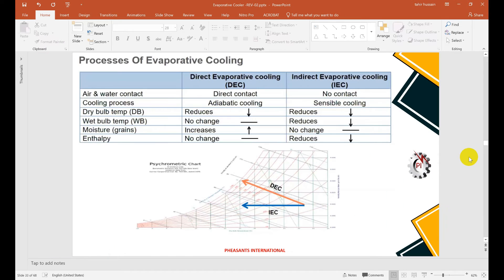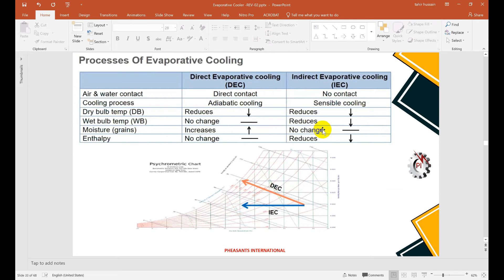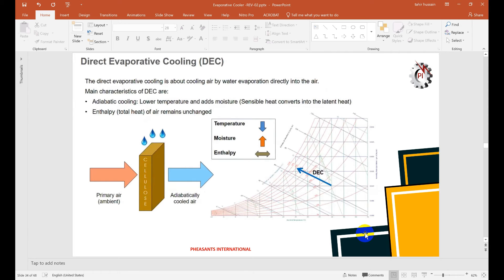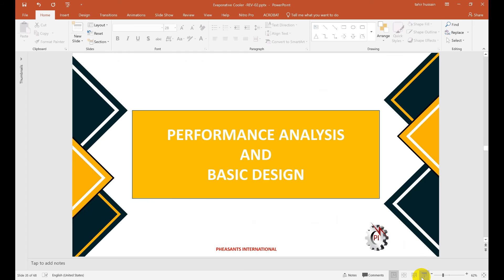In direct evaporative cooling (DEC): direct water-air contact, adiabatic process, dry bulb temperature reduces, wet bulb temperature stays constant, moisture content increases, enthalpy remains constant. In indirect evaporative cooling (IDEC): sensible load reduces, no moisture-air contact, dry bulb temperature reduces, wet bulb temperature also reduces, specific humidity and humidity ratio remain constant, and enthalpy is reduced. The conventional DEC process follows constant wet bulb temperature and constant enthalpy — it is an adiabatic process.